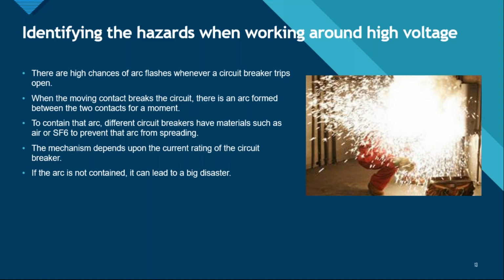When the moving contact breaks the circuit, an arc forms between the two contacts for a moment. To contain that arc, different circuit breakers use different materials or elements, such as air or vacuum. Since there is a vacuum, there is no medium for the arc to spread, so the arc will be contained. Or there might also be SF6 for the transformer circuit breakers to prevent that arc from spreading.